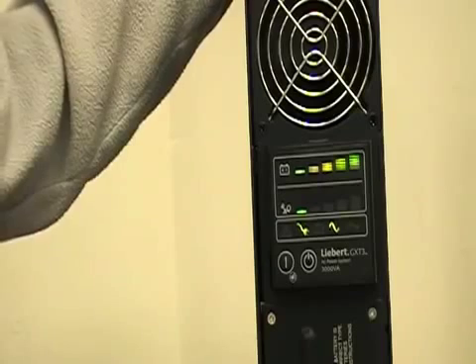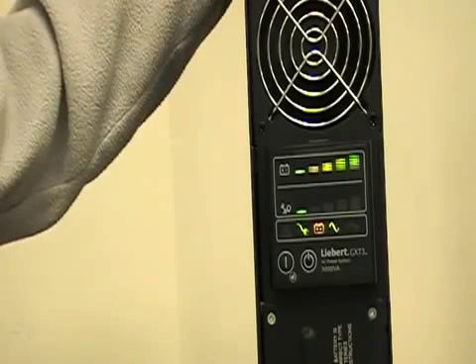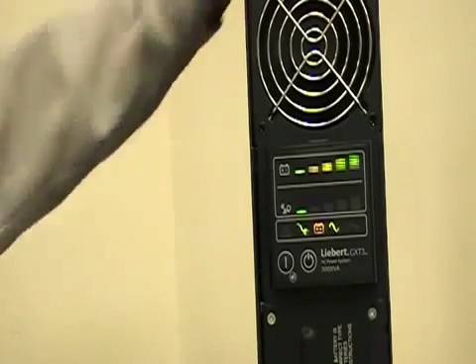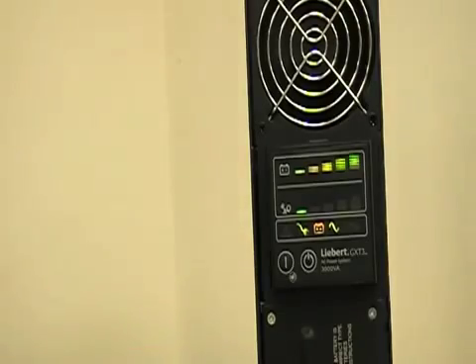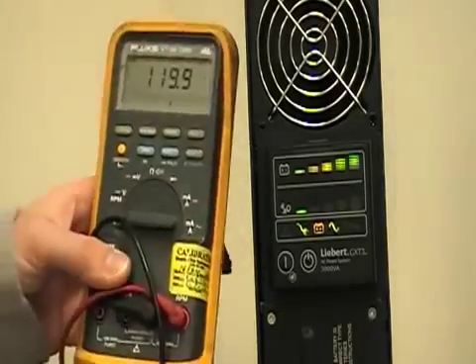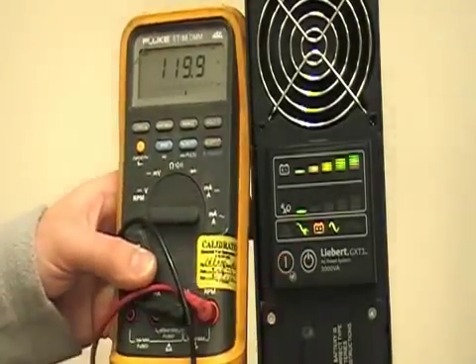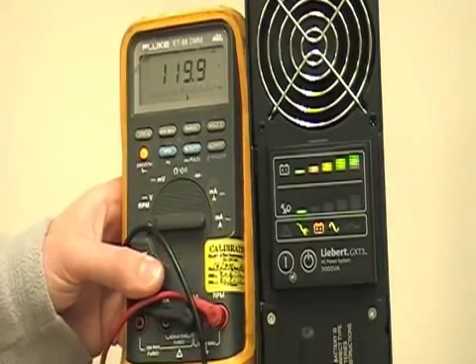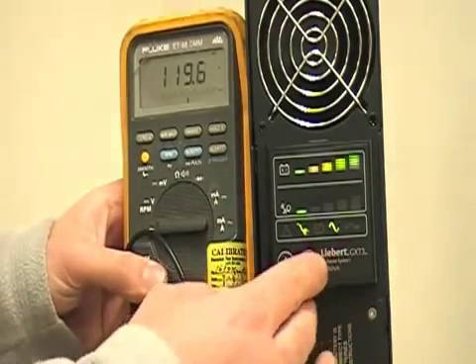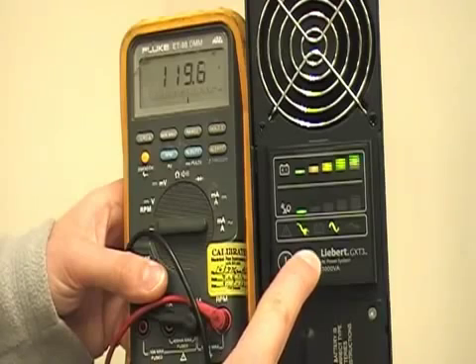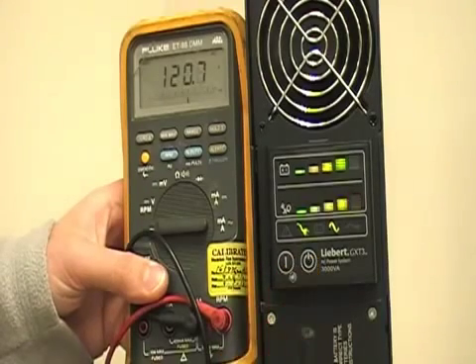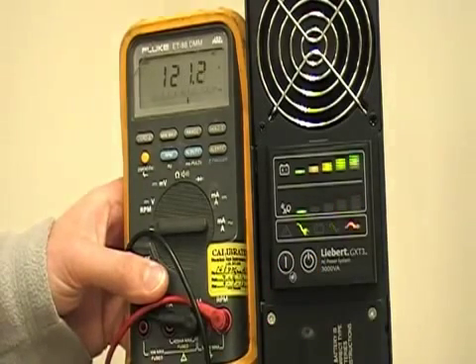That's basically what that'll do. So, about a 30-second battery run is what that line does, and you'll notice it does not shut your output off by hitting that line. So the only way to shut the unit off is to transfer to bypass with the circle on the line, then go ahead and remove your cord.